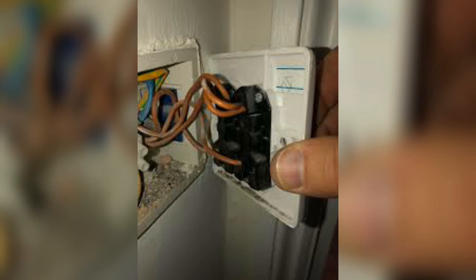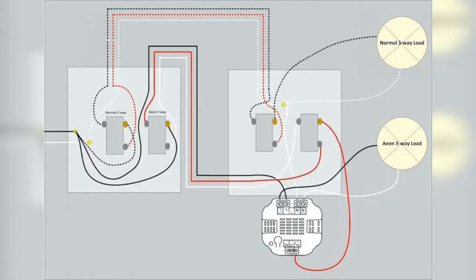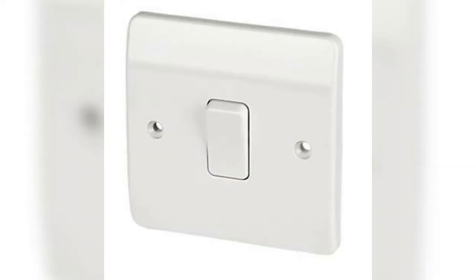Two or three wires will be attached to the switch. An incoming hot wire, which is black, a return wire which carries the load to the fixture and may be black or red or any other color except green, and sometimes a grounding wire, which is green or bare copper. There may be other wires in the box, but you are only dealing with those connected directly to the switch.